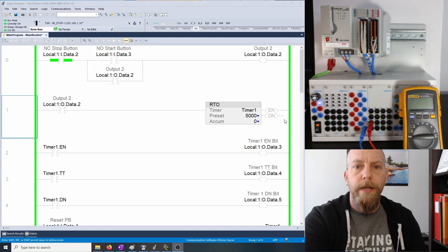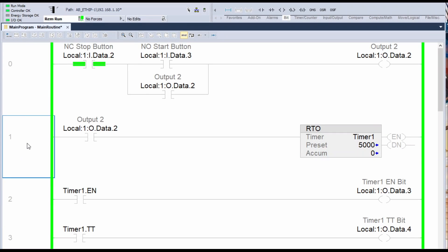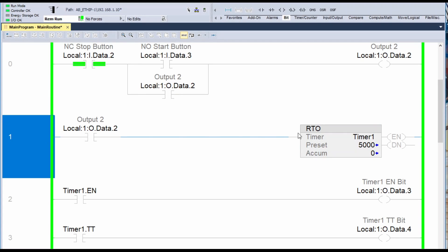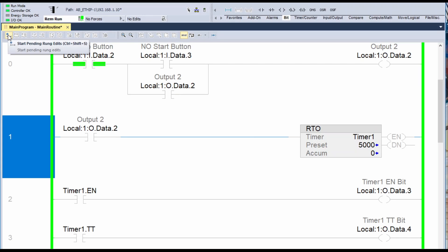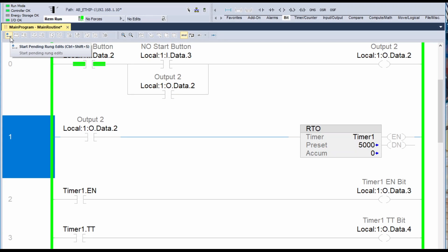So let's do some online editing of our program. Let's zoom into our program and look at rung number one right here. Maybe I want to change the timer type and maybe I want to change the preset value as well. In order to change this rung and do some online editing, up here we have this one called Start Pending Rung Edits. It also has the quick keys Control Shift S. I can click on this, or hit Control Shift S, or the easiest way is just to click on the rung that I want to edit. Once it's blue, then you just hit Enter.